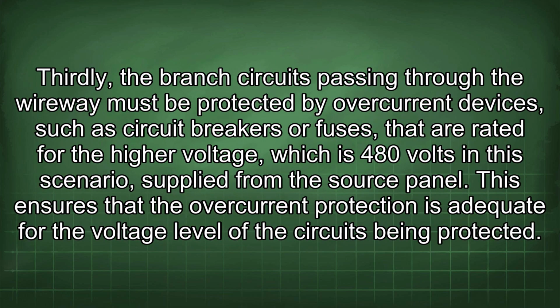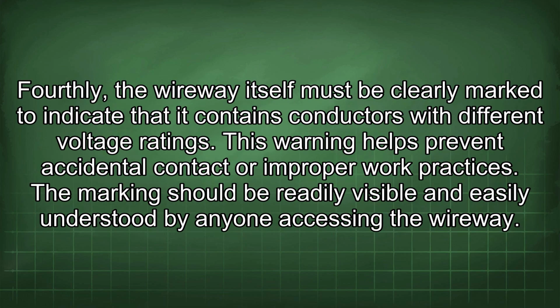Thirdly, the branch circuits passing through the wireway must be protected by overcurrent devices, such as circuit breakers or fuses, that are rated for the higher voltage, which is 480 volts in this scenario, supplied from the source panel. This ensures that the overcurrent protection is adequate for the voltage level of the circuits being protected. Fourthly, the wireway itself must be clearly marked to indicate that it contains conductors with different voltage ratings. This warning helps prevent accidental contact or improper work practices. The marking should be readily visible and easily understood by anyone accessing the wireway.